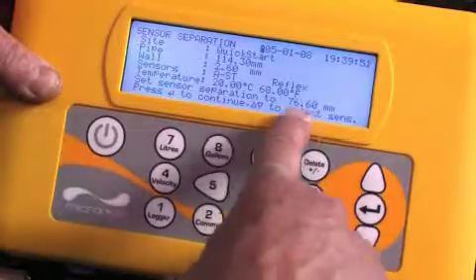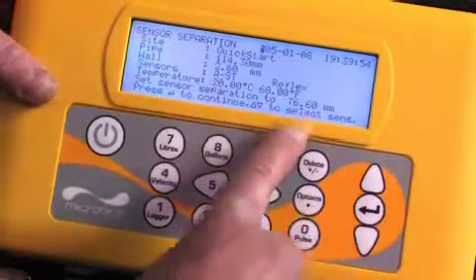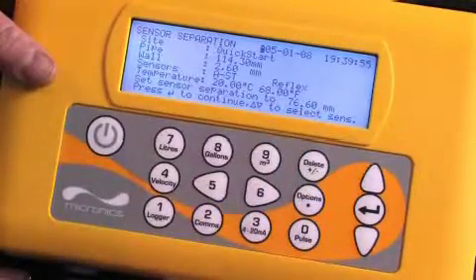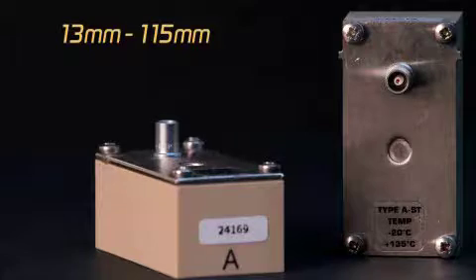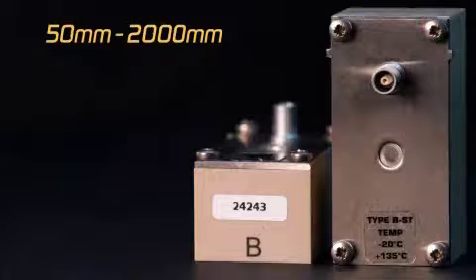In this case, seventy-six millimeters, ensuring that the right type of sensor is selected. For the standard sensors, the pipe sizes are 13 to 115 millimeters. Depending on the information entered, you may need to use other sensors if available for other pipe ranges. B standard sensors are for a pipe range of 50 to 2,000 millimeters.